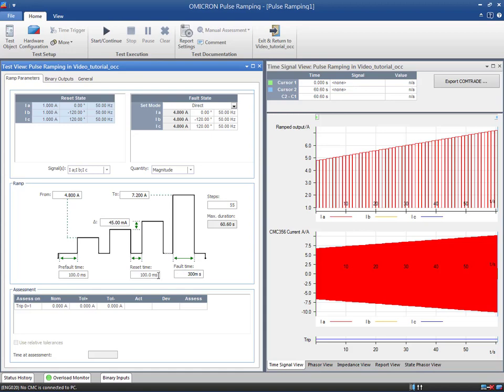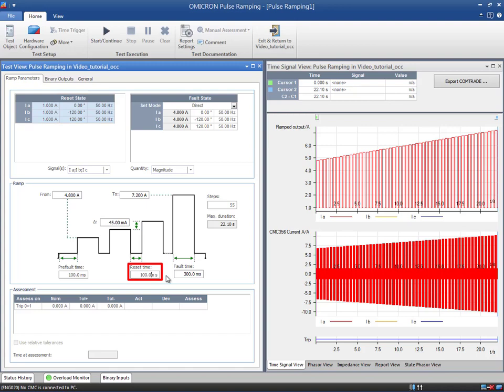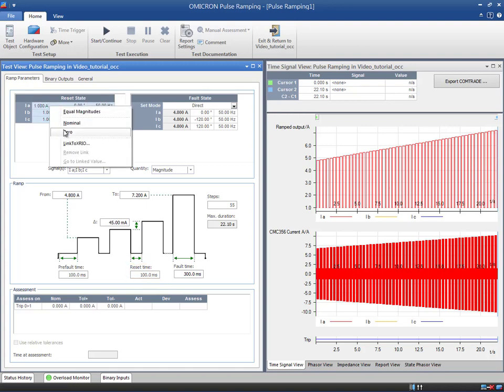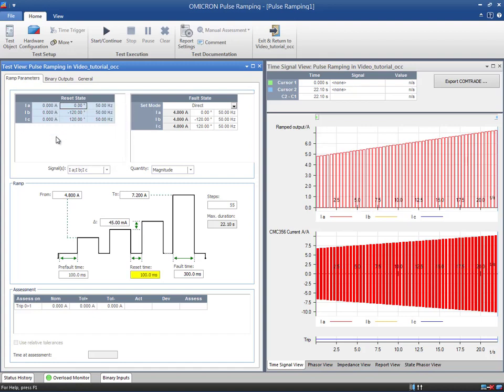In order to measure the high set, the reset value must permit the relay to drop off. The reset state will be applied in between two pulses during the reset time. To avoid any confusion, the current has been set to zero and the duration to 100 milliseconds. This is long enough for the relay to drop off between two pulses.